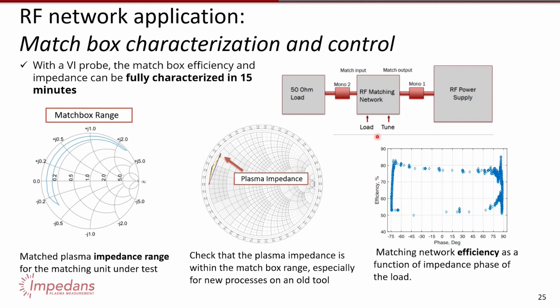Where all you need to do is switch to a slightly different matchbox, and all your matchbox problems go away. Okay. We've had feedback from quite a few customers on this. Matchbox mapping is usually done using a vector network analyzer, which means you're mapping it at like 1 watt because that's all it can output. And it's a very, very slow process because VNAs are not typically very user-friendly. You have to do everything manually on this box and export data from it. And I've heard that matchbox mapping could take up to 2 days if you're doing a very serious project.